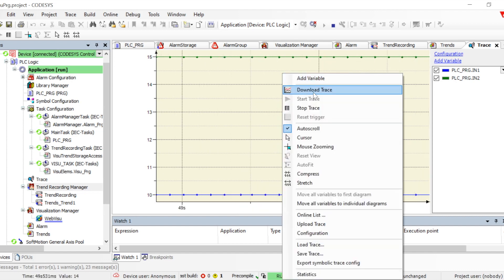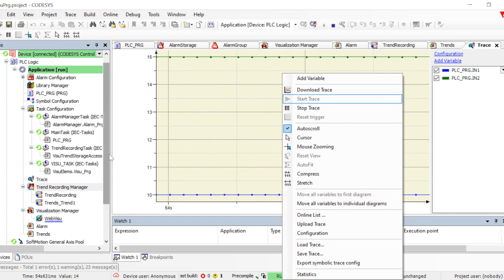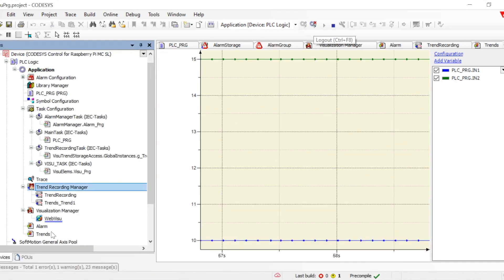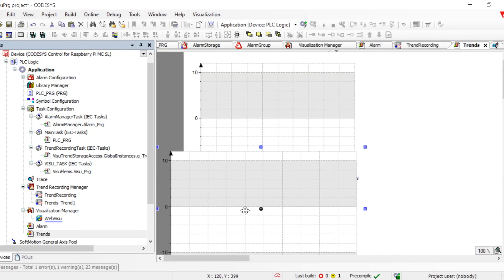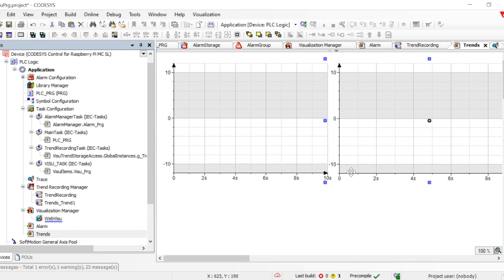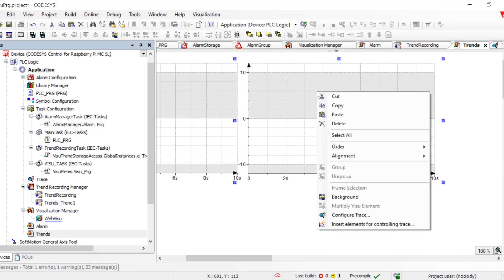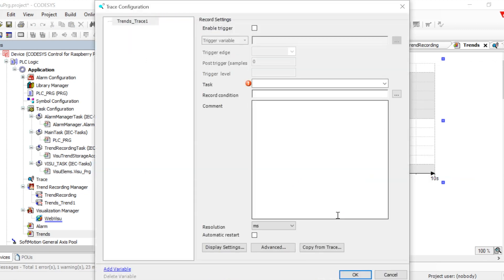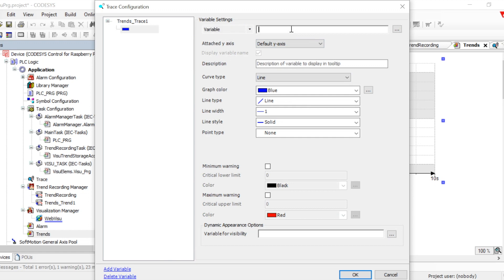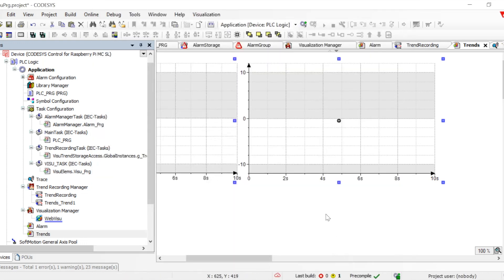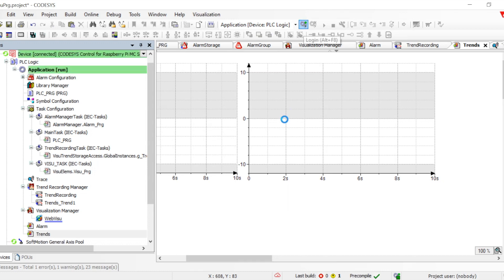If we want to put the trace in the visualization, we can do that too. Let's go to the visualization and try to add the traces there using Special Controls. We can then configure the trace — same way, we add the data, define the task where it will be running, and add the variables. All steps remain the same; the difference is this will be shown on the visualization, so once it's on the visualization, you can see it on a web page using web visual, or the target visual will show it on a local HMI.